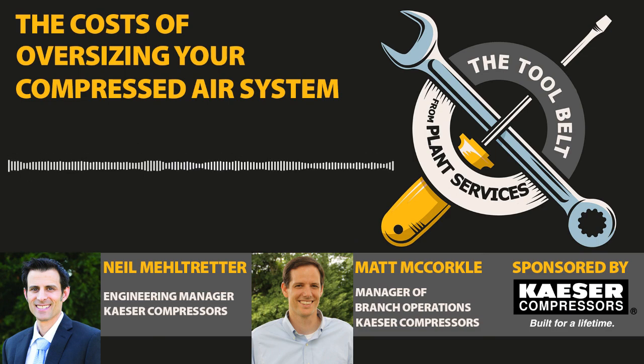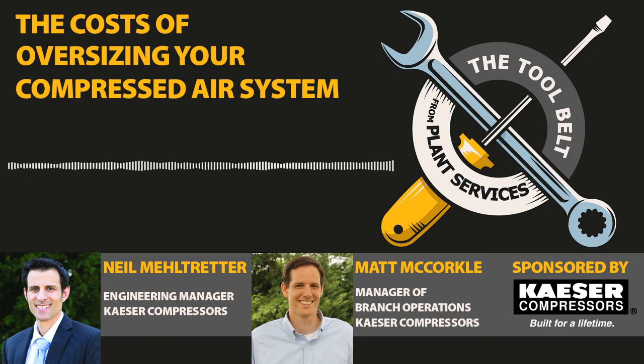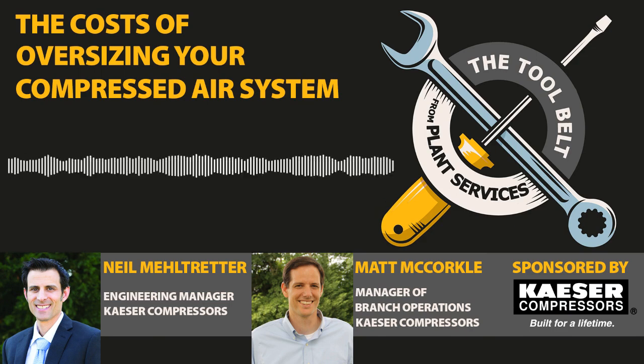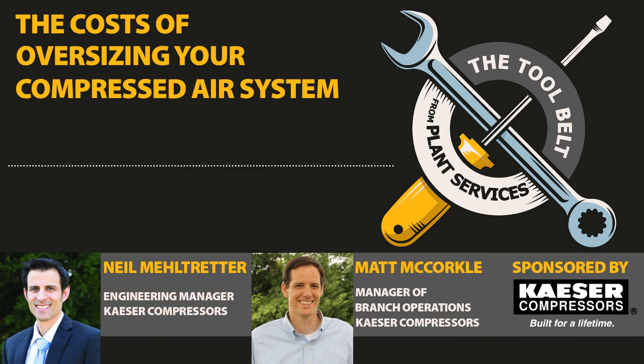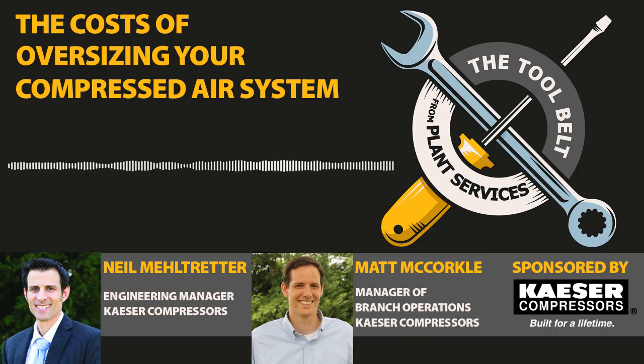There's a lot of different control types out there. Variable frequency drive, also called variable speed drive. You have to look at, does it have one compressor that's meeting the load? If that's the case with a VFD, typically those are sized so that between 40 and 85% they're most efficient. So that's another number you can look at. A lot of the machines out there can show you duty cycle or percent capacity, and that's a great indicator.